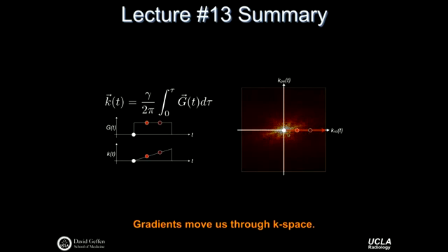While we're moving through k-space, this is a dynamic process, but every time we're at a point in k-space, we're getting hundreds or thousands of samples in our receiver coil, because everything I'm showing you here is really in the rotating frame. You have to remember, in the lab frame, our protons are still zipping around at the Larmor frequency. So for the brief period of time, even if it's just microseconds, that I visit this position in k-space, my spins have zipped past my coil maybe 1,000 times. They're fluxing into my coil and allowing me to receive a signal that accords with that particular point in k-space. And I'm just continuously moving out along this, say, x-axis, which is frequently referred to as the readout axis, as a function of time. So importantly, through this equation and this example, we appreciate that gradients are what move us through k-space.